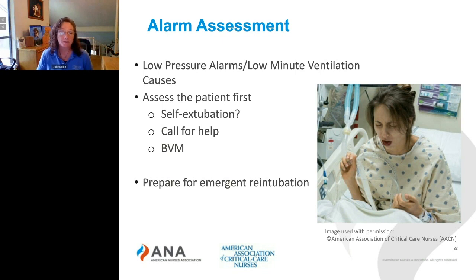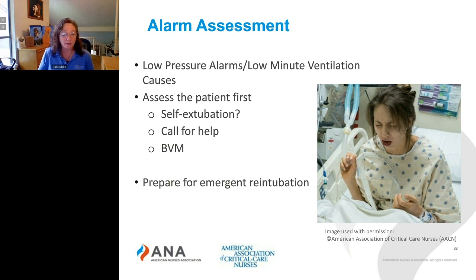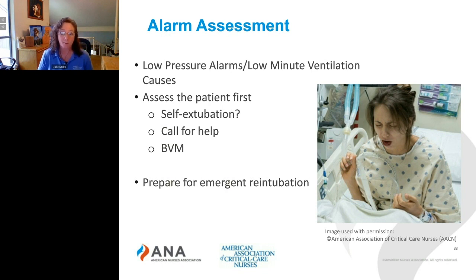Another cause of low pressure or apnea alarms is self-extubation — the patient pulls the tube out themselves. Sometimes tubing near their hand gives them a grip and out it comes. Patients can also be creative: I've seen patients use their tongues to pull the tube out. If self-extubation happens, call for help, use a bag valve mask to support ventilation, and prepare for emergent re-intubation.